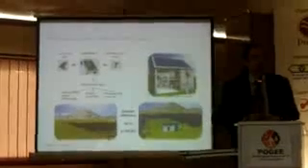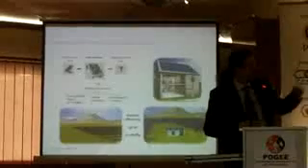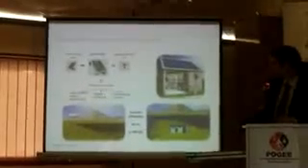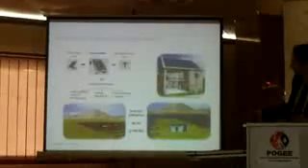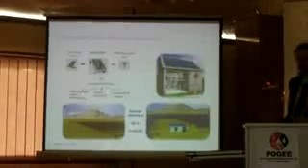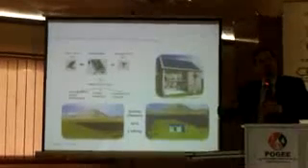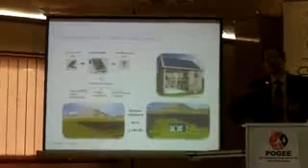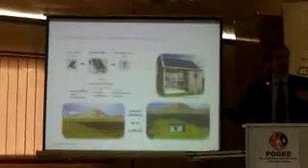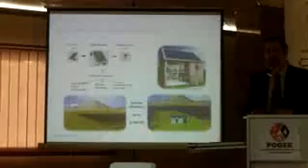Now you see here 2 types of how to roll out a megawatt plant. On the left side, you see the module field, and string inverters, small inverters of maybe 10 or 20 kilowatt, directly mounted below the module. There the DC cabling stops, you collect the AC cable and evacuate it via a medium voltage transformer to your medium voltage grid, 11, 33, 66, 132.